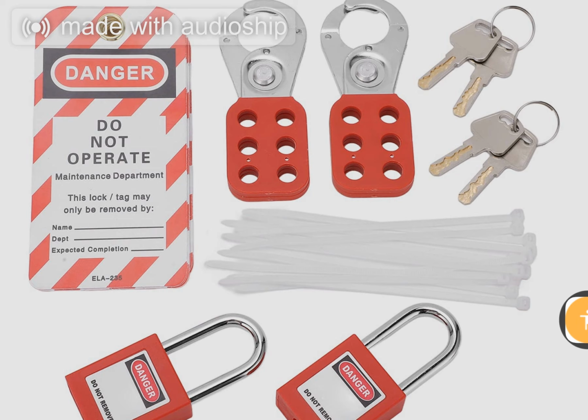Okay, on to step 5, stored energy check. This is a big one. You can isolate the main power, but residual energy can still be lethal. You're talking about things like capacitors. Exactly. The documents specifically call out discharging capacitors. And for you, the learner, you need to understand a capacitor can hold a massive, deadly charge long after the breaker is open. It's a silent killer. So you have to bleed that energy off safely. You have to. If you skip this, you can still have a fatal accident from stored energy alone.